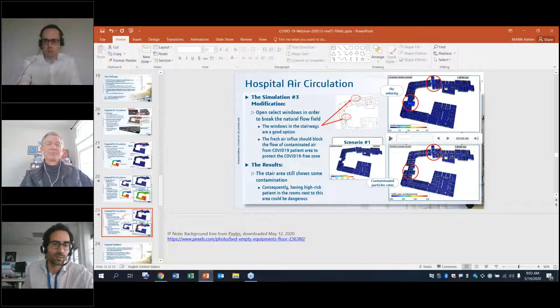In fact, if you look at the velocity fields here, and in the meantime, if you look at the contamination ratio of the particles, you will see that the safe area is now much more protected than it was in the current state of the hospital. And in the meantime, thanks to the opening in the middle of the COVID area, we are pushing basically the air on both sides, but especially on the square where COVID patients are ill, and we are reducing a lot the contamination in the corridor. And this is basically the solution that the director of the hospital is using right now to protect more the medical staff.